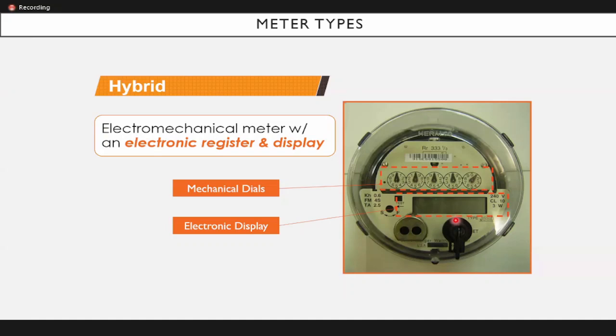Today, automatic or remote meter reading is the most common application of electronic registers on electromechanical meters. These registers typically detect the disk rotation using some form of optical detector and communicate the energy consumption to a nearby meter reader or central system. Communication may be by radio frequency or RF, power line carrier, telephone, cable, or other appropriate media.